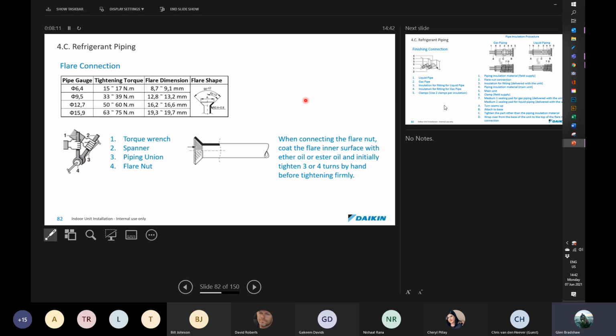I think the thing that was missing was him actually cleaning up the piping. I think he had done it, but it's just something to remember in terms of doing flares. A lot of times when we come across refrigerant leaks, we still find that the biggest culprit for leaks is badly prepared pipe ends before the technicians actually flare them.